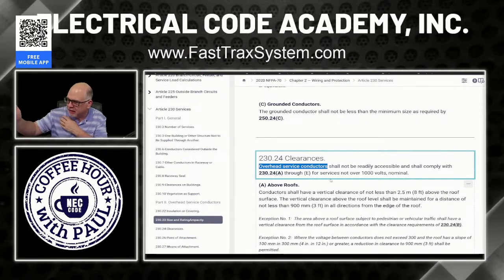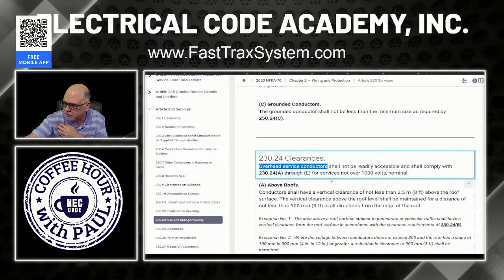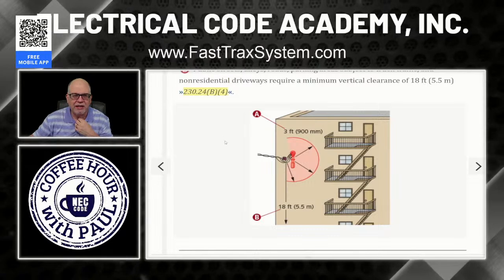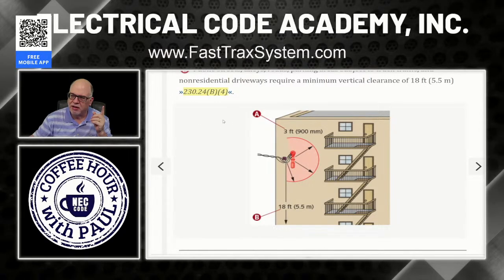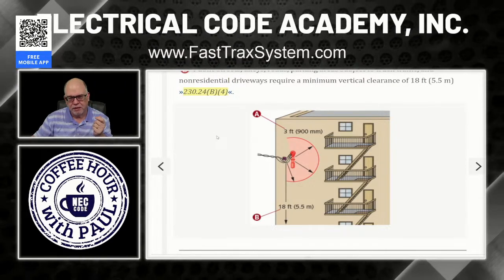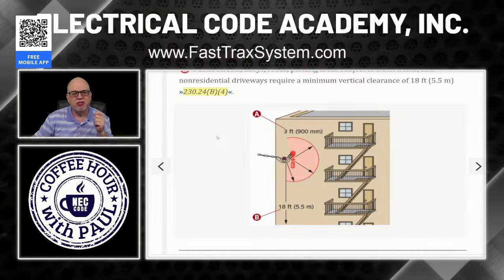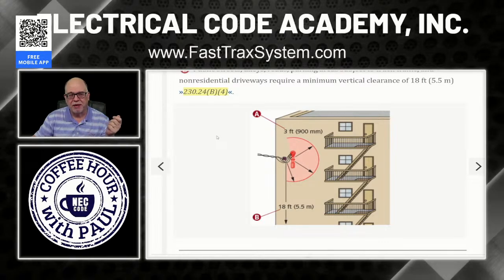So before we read any more about this, I kind of prematurely took us there. Let's go back real quick to the image so I can explain something. Now, if the transformer was out here, and it's a utility transformer, and it dropped from the pole to right here, then this would be under the exclusive control of the utility. So based on 90.2 of the NEC, that is outside of the scope of the NEC. And if it's outside of the scope of the NEC, then 230.24 can't apply.